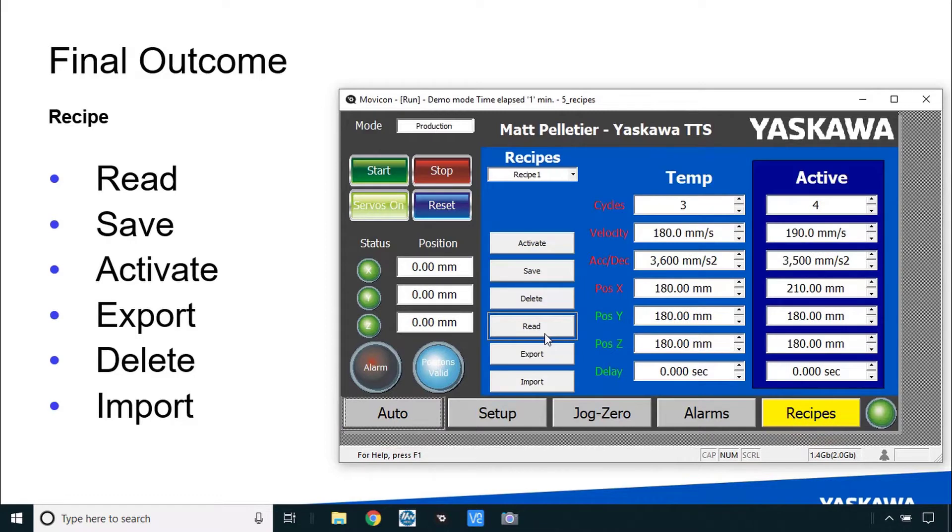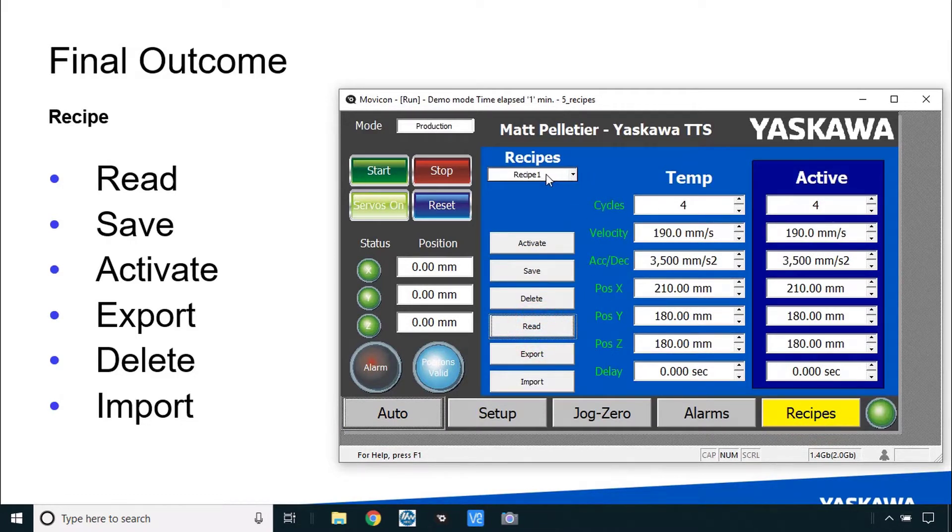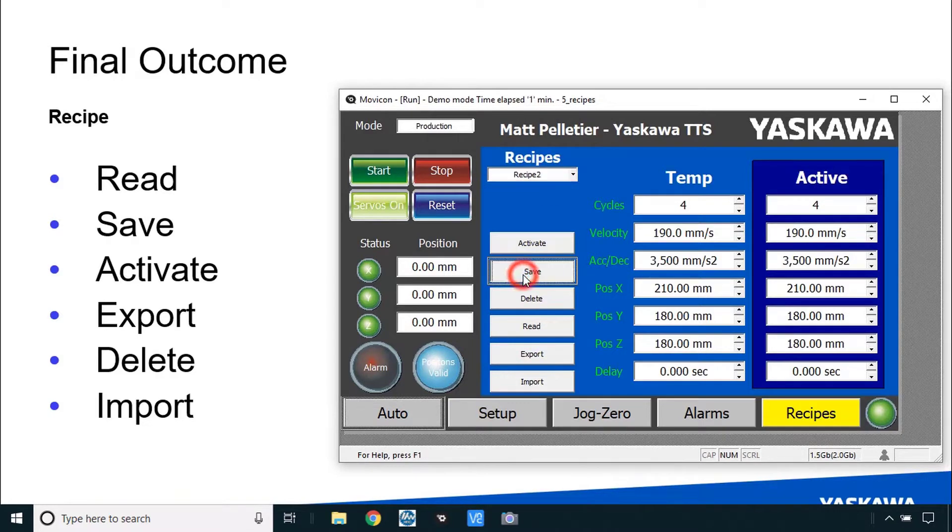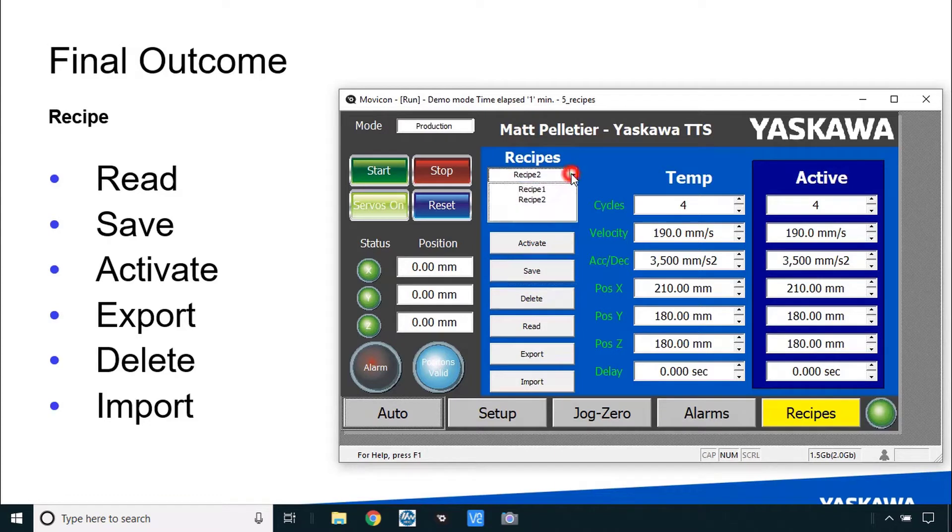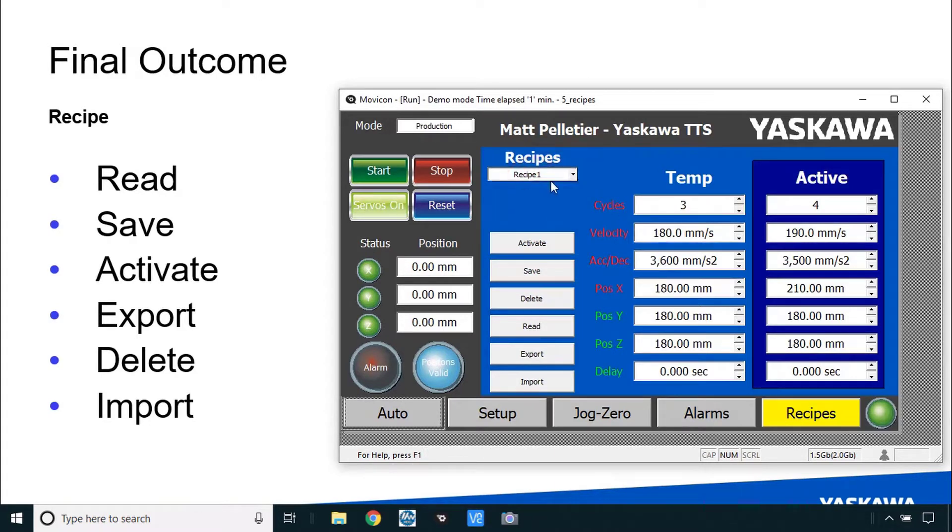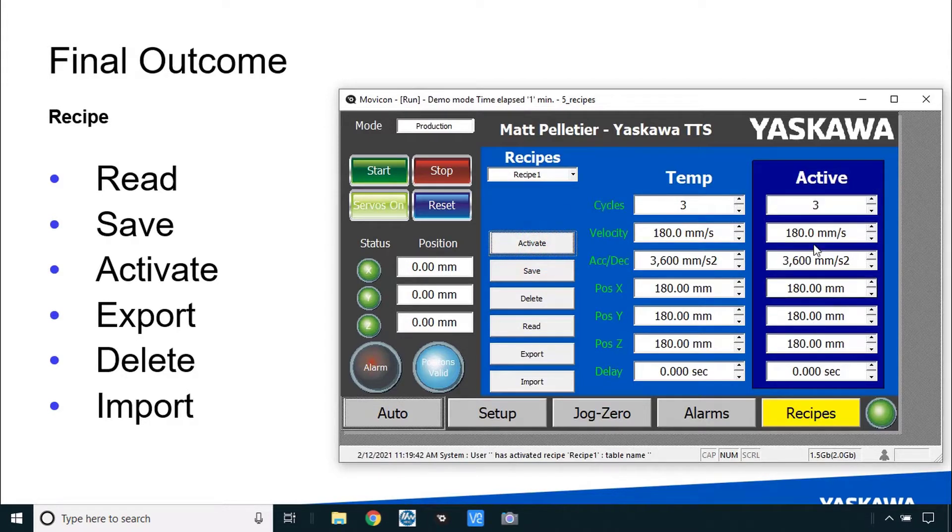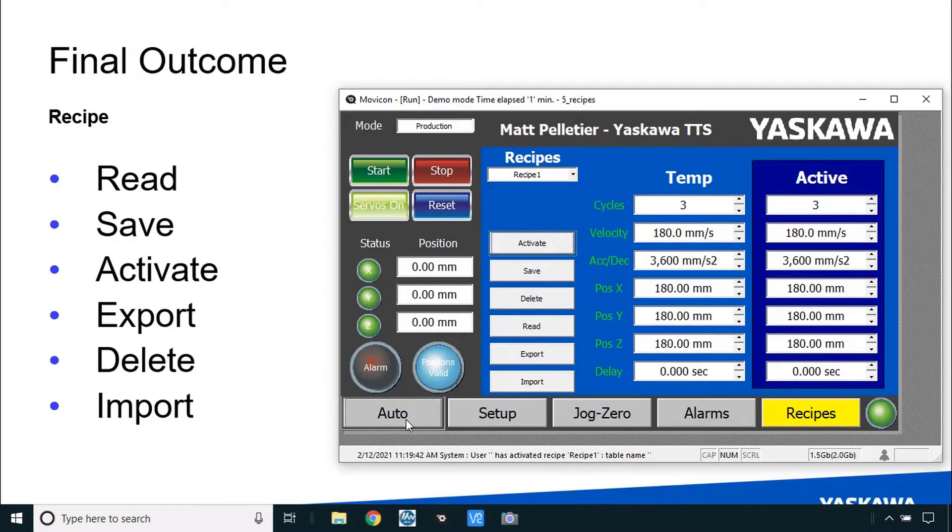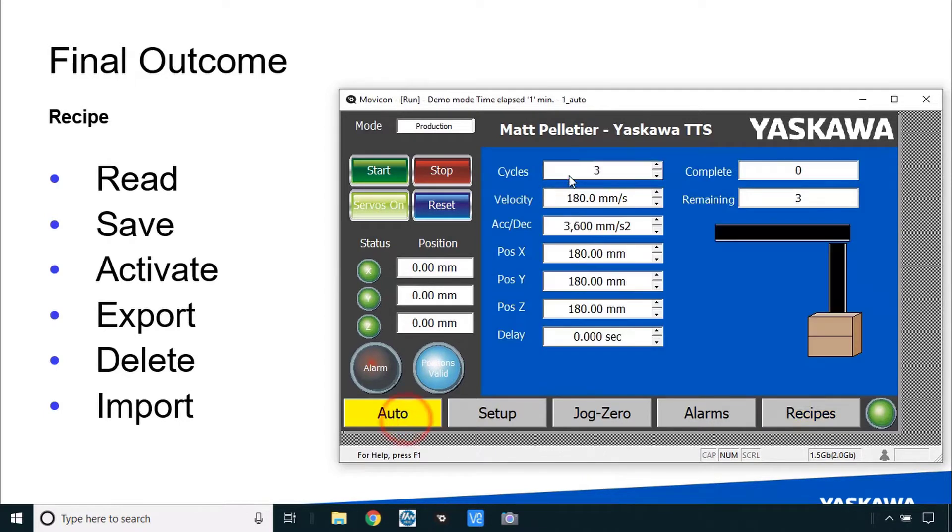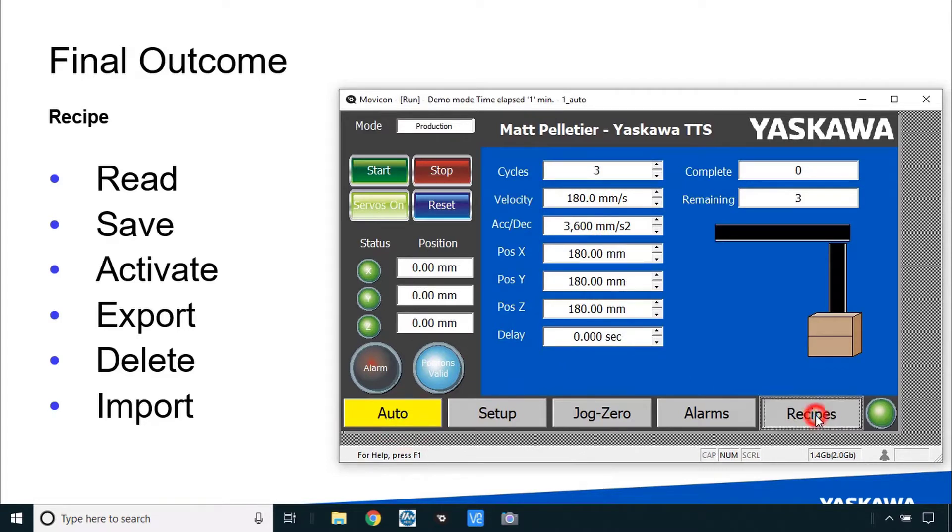The active values read those in to the temp values, temporary values of the HMI. Type in a new recipe name and then save that data. Now I could go back to recipe 1 that loads the saved data into the temp area and I can activate it which writes it over into the active area. This column here is identical to the column of data here in the auto screen.